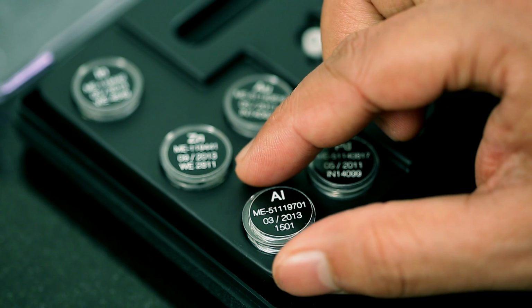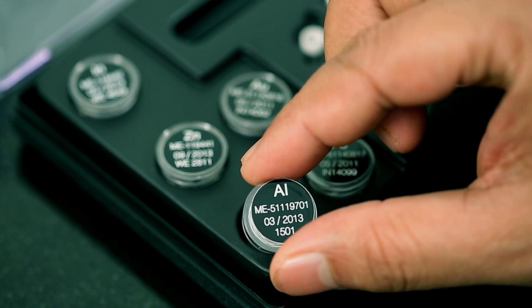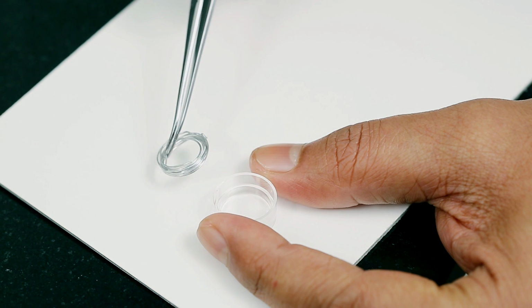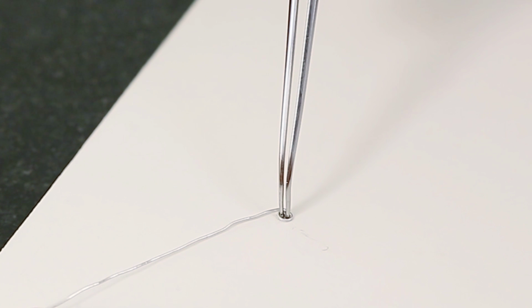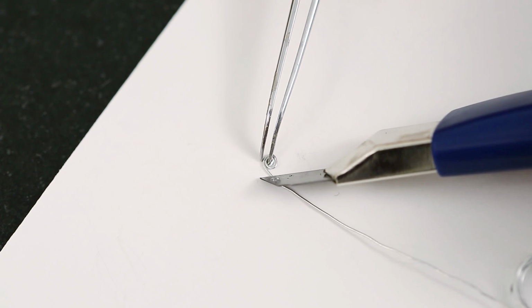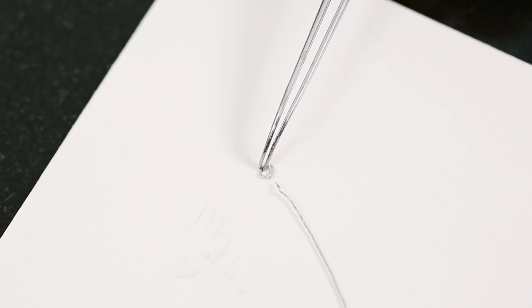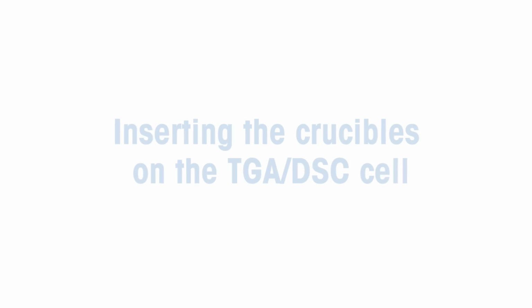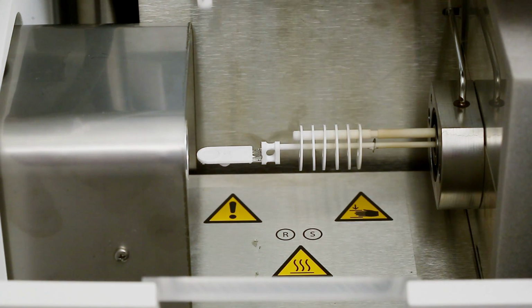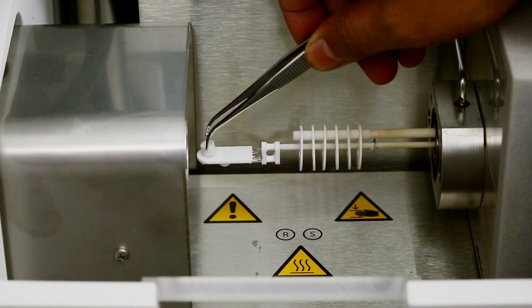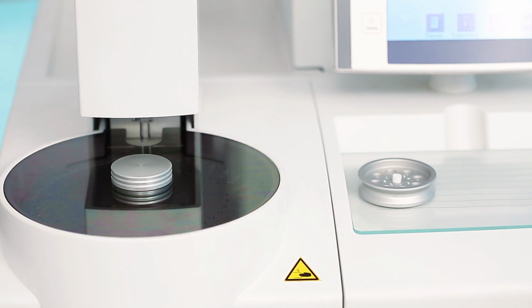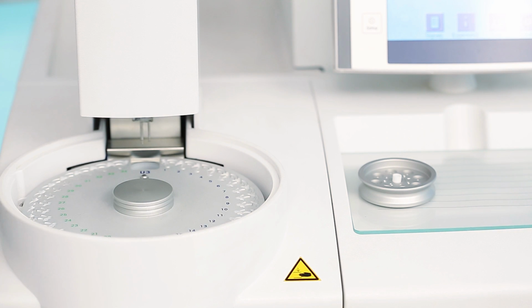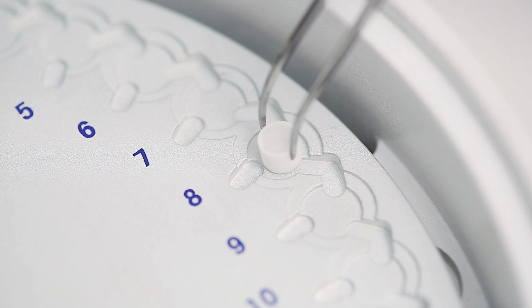Let's start with the preparation of the calibration substance. Cut approximately 10 millimeters of aluminum wire in order to achieve the necessary mass and wrap it around the tips of tweezers. For built-in DSC and DTA sensors, make sure that an empty reference crucible is placed on the respective position. Place the empty sample crucible on the position of the robot turntable you specified in the software.